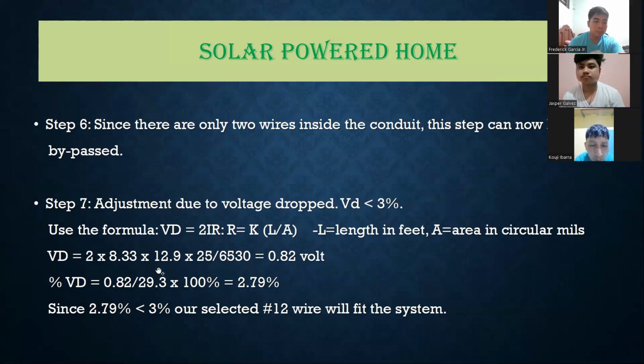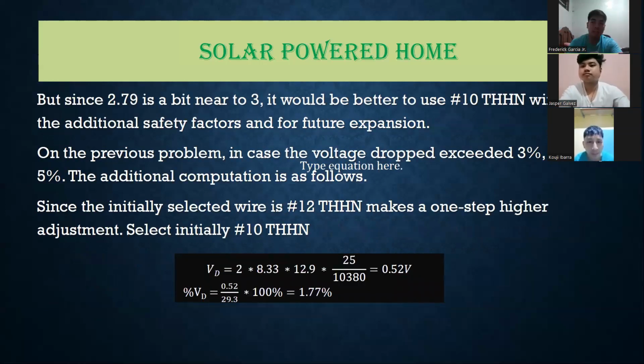Now we find the percent of voltage drop, so we divide that by the voltage of the photovoltaic cells, times 100%, and we get 2.79%. Now, since 2.79% is less than 3%, the selected number 12 wire will fit the system. But since 2.79 is a bit near to 3, it would be better to use the number 10 THHN wire for additional safety factors, and of course if we want to expand in the future.